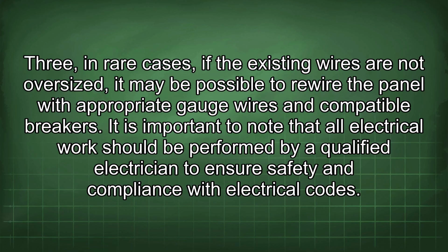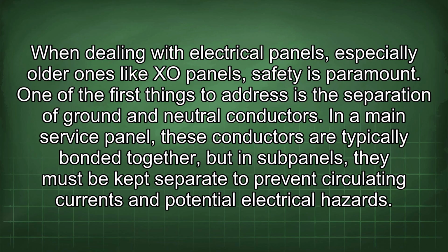It is important to note that all electrical work should be performed by a qualified electrician to ensure safety and compliance with electrical codes. When dealing with electrical panels, especially older ones like XO panels, safety is paramount. One of the first things to address is the separation of ground and neutral conductors. In a main service panel, these conductors are typically bonded together, but in subpanels, they must be kept separate to prevent circulating currents and potential electrical hazards.